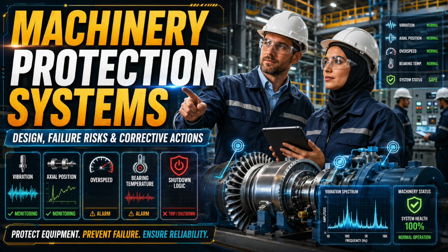But casing vibration is often misunderstood. Shaft vibration and casing vibration are not the same thing. A shaft probe tells you how the rotor moves relative to the bearing. A casing accelerometer tells you how the external structure responds. That response depends on bearing condition, machine stiffness, foundation, mounting, resonance, loading, and frequency content. So if you use casing vibration for protection, you must define what you are actually protecting against.